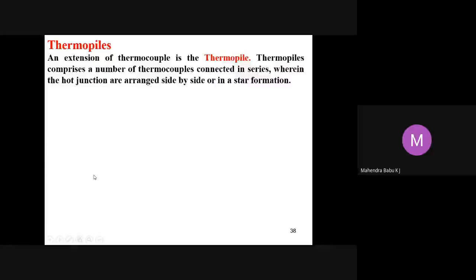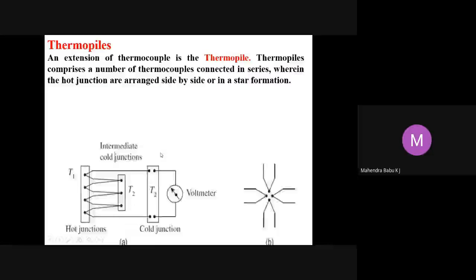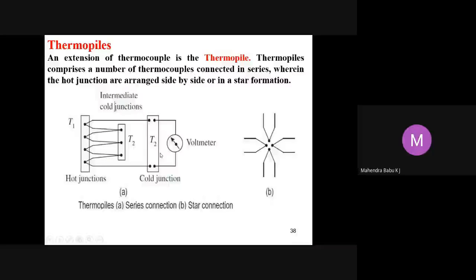So next we have another type of sensor, that is a thermopile. This is an extension of thermocouple, where a thermopile comprises a number of thermocouples connected in series, wherein the hot junctions are arranged side by side or in the form of a star. So that you can see it here. They are arranged in series. Thermocouples are arranged in series or in the form of a star. So this is known as a thermopile. So in such cases, the total output is given by the sum of all the individual EMF.